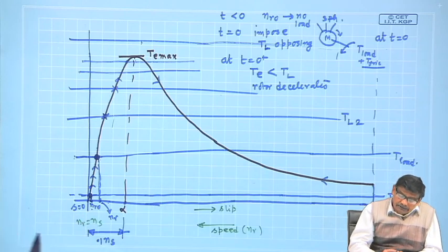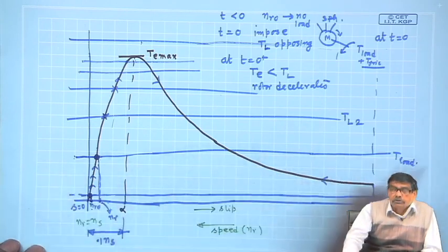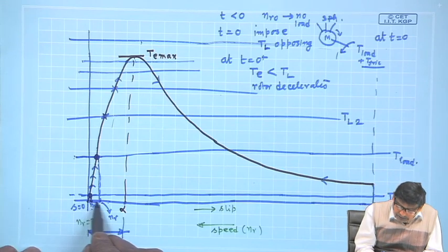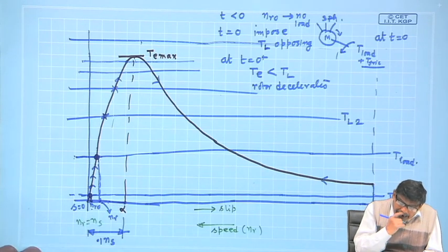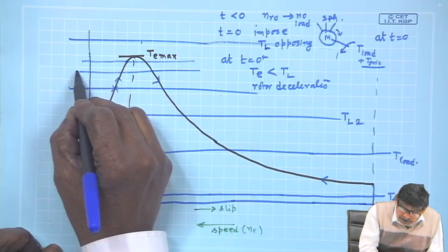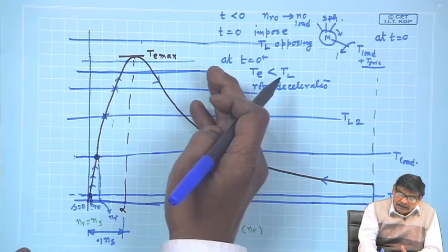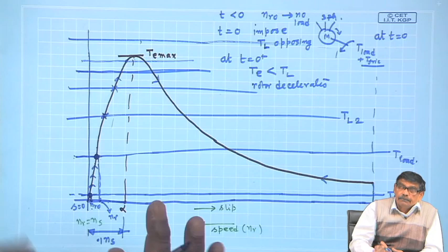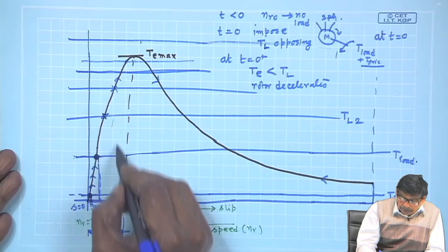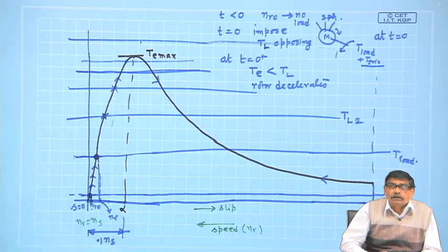So, when you increase the load torque on the shaft of the machine, you should be a bit careful. Suppose somebody has increased it, okay, the machine is capable of producing this much torque, let me put this torque, it will run, and let this be called the full load torque, and the machine is designed to run at this full load torque, then it will run at this speed. But this is not advisable.